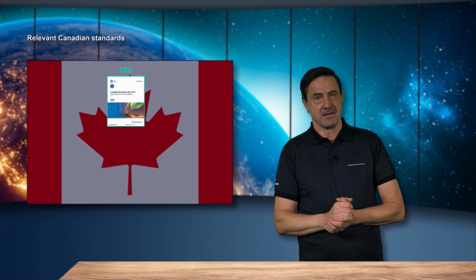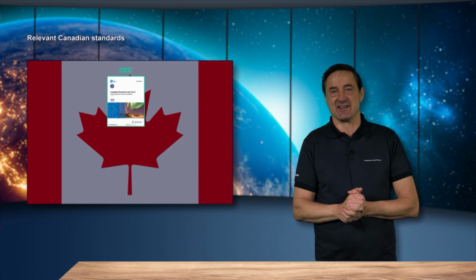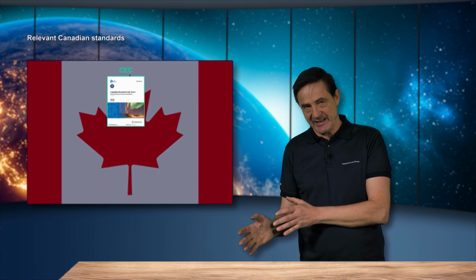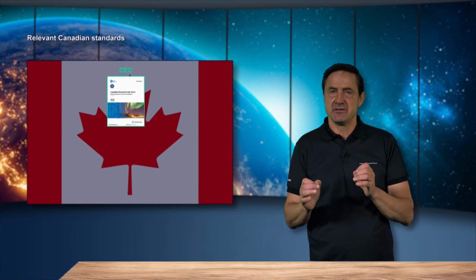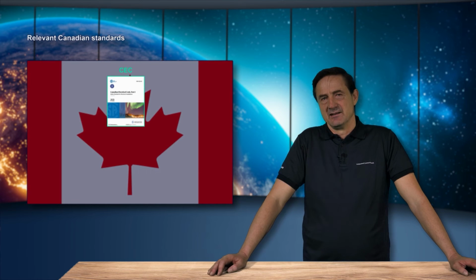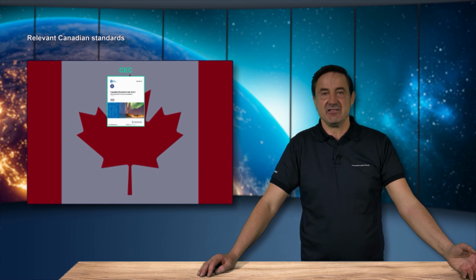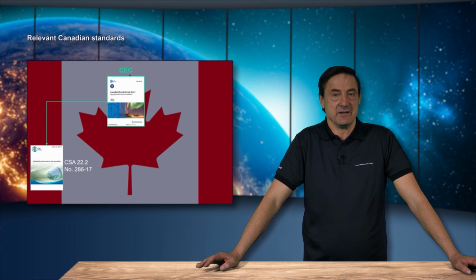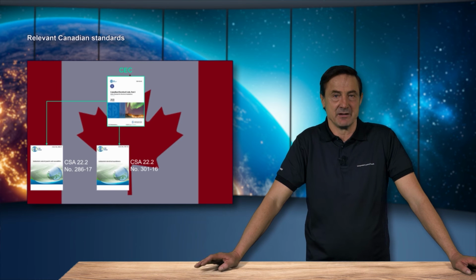The same philosophy can be found in Canada, but of course with CSA codes and standards. Comparable to the NEC in the US, the fundamental principles and requirements for electrical installation are covered in the CEC, the Canadian Electrical Code. And similar to the NEC, it refers in Appendix A to the CSA standard number 286 for industrial control panels and to the CSA standard number 301 for industrial machinery.